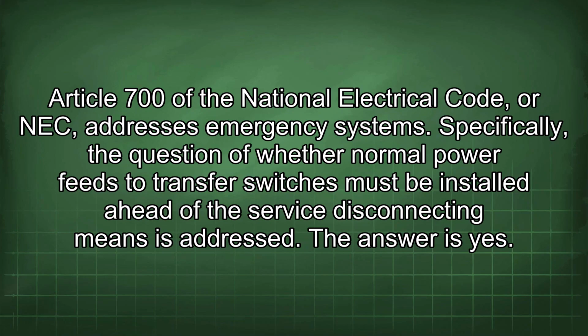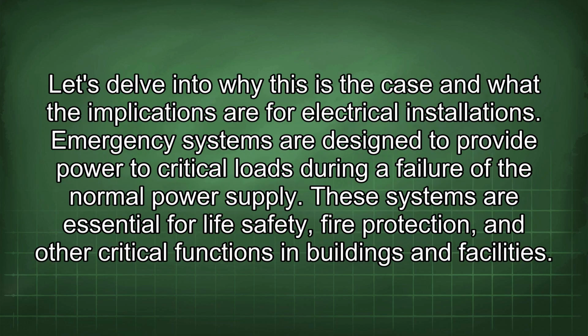Article 700 of the National Electrical Code, or NEC, addresses emergency systems. Specifically, the question of whether normal power feeds to transfer switches must be installed ahead of the service disconnecting means is addressed. The answer is yes. Let's delve into why this is the case and what the implications are for electrical installations.